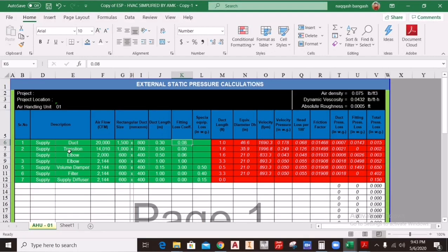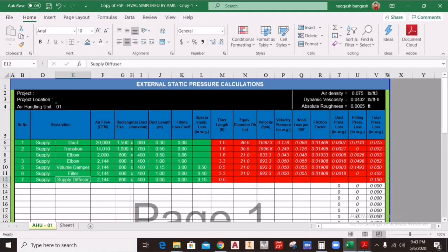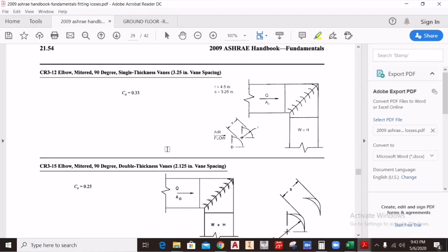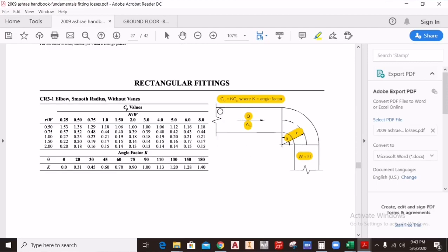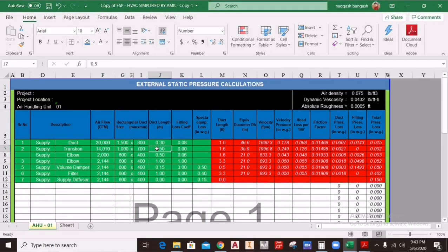We will calculate the fitting loss coefficients for a transition, elbow, elbow with damper, volume control damper, filter, and supply diffuser. Starting with the elbow, we use the ASHRAE Handbook 2009 for rectangular fitting losses. The equation is C0 = k × Cp. C0 is your fitting loss coefficient value, which you calculate from the ASHRAE handbook and enter into the sheet. For this you need the duct size, CFM, and duct length.